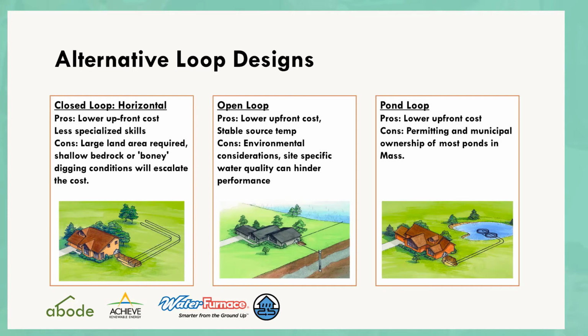It's very common, and there's a lot of space required, so in urban areas, this is usually a no-go. Open loop systems in our area are done with a standing column well configuration. Water is pumped out of the well, processed through the equipment, and then returned to the well, with the return point and the pump intake being at opposite ends of the well. Depending on a variety of factors, the pump would either be at the bottom or the top.